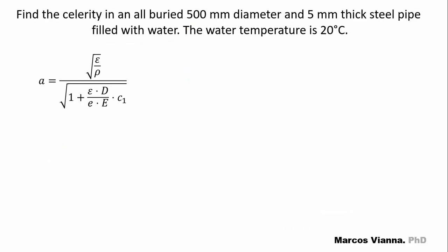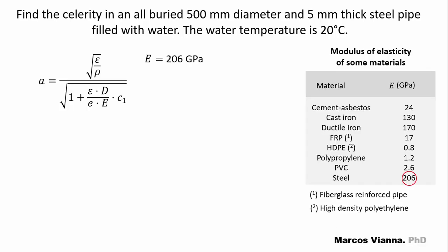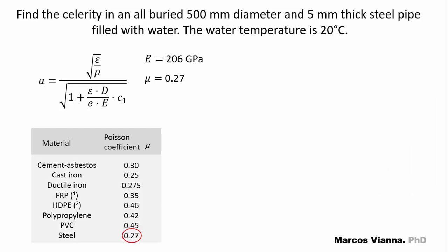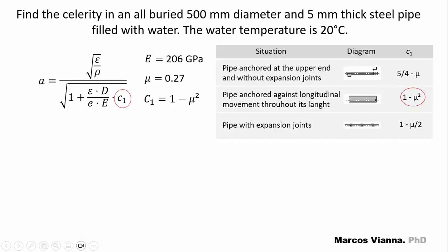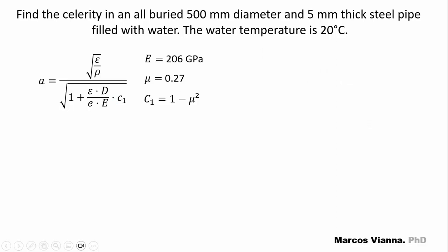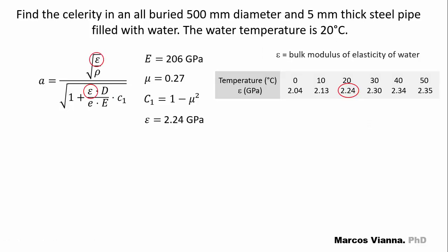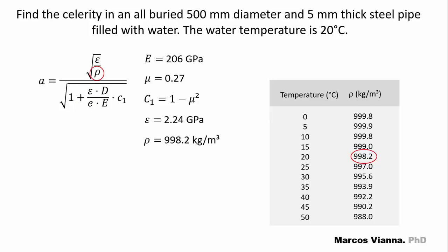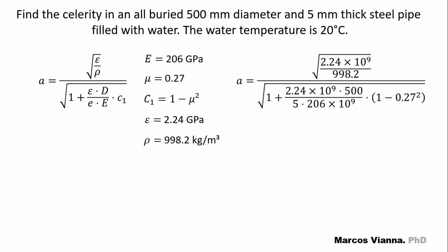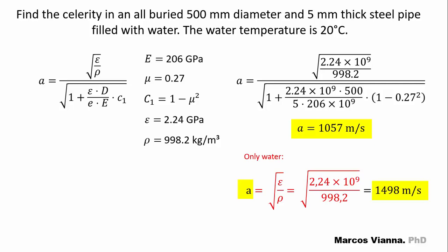Let's do an example. Find the celerity of the water inside the pipeline with these characteristics. Here is the elasticity modulus of steel and its Poisson coefficient. This one will be the C1 factor. And now the water characteristics. This is the elasticity modulus of water and this is its specific mass. We substitute the values and find this value. It's fast, but not as fast as in the water.